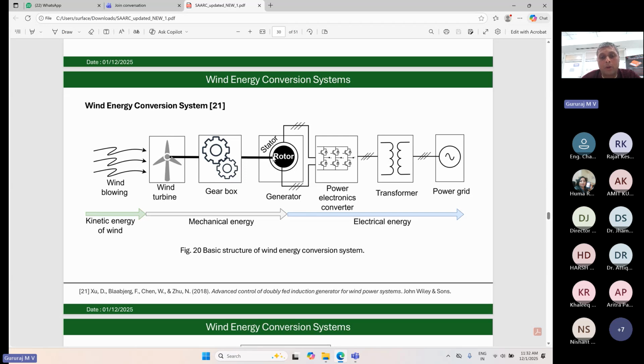And then this is coupled to the rotor of the generator, and then the stator is connected to the grid. We may use different types of generators. I'll discuss especially the type 3 generator. Ultimately, you need power electronic switches and converters to actually synchronize with the grid, because the wind power is highly fluctuating. You may have to convert AC to DC and then from DC to AC. So you need inverters, and because we have inverters, we need filters, and then the transformer to meet the voltage levels as per the power grid requirement.